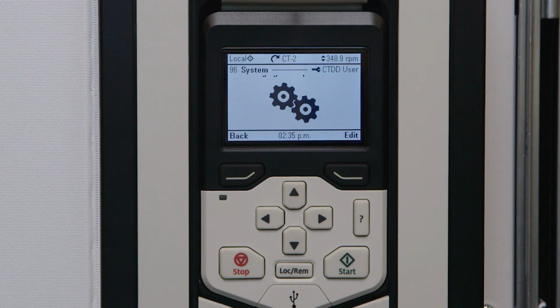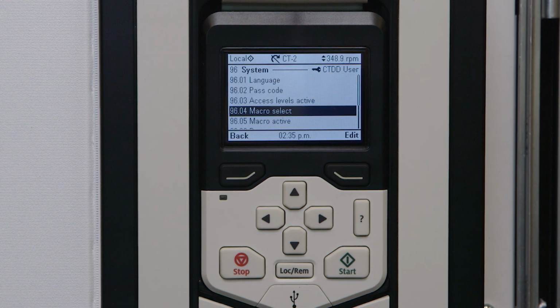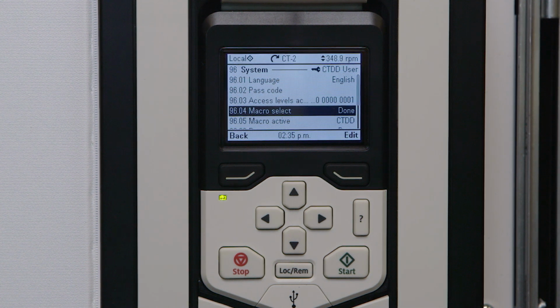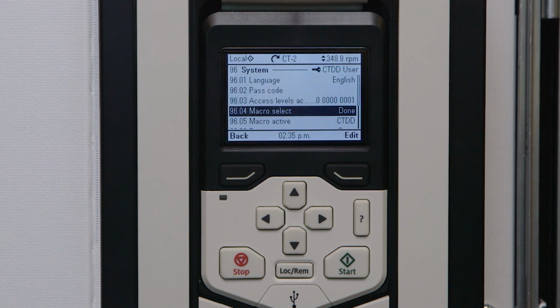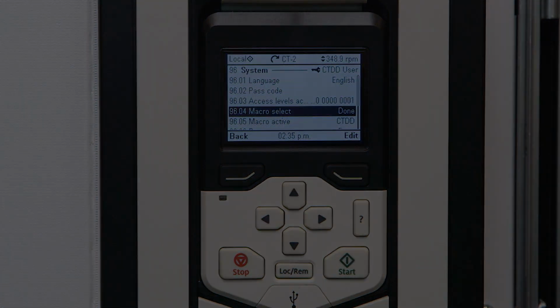Warning: resetting the VFD parameters back to the default settings will undo all of the settings outlined above except for the motor data and serial communication data. These two will not be reset. All other changes will be lost.